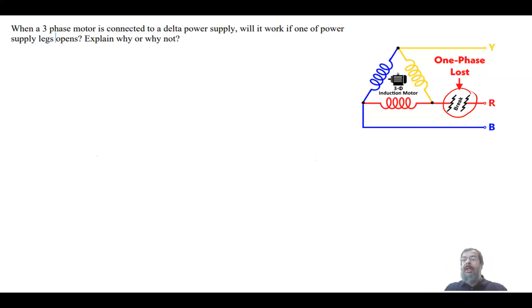Plus the torque: instead of having a rotating magnetic field, you will have a pulsating magnetic field, so you see the speed changing too much. That can burn the motor. There's too much torque applied to the rotor which can really damage the motor.